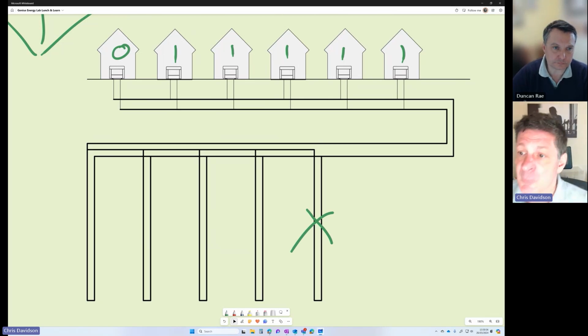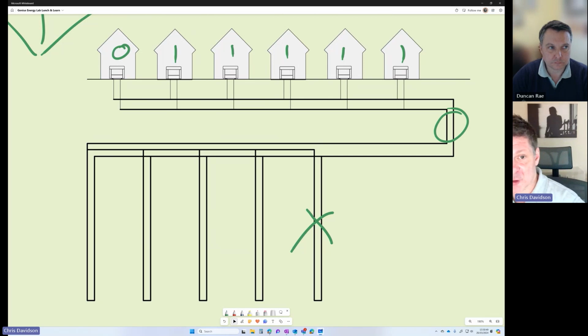On the other hand, the water required for all those heat pumps has to be accommodated in the header pipes that transport water from the buildings to the ground and back, and therefore these pipes get bigger. So there's a penalty to pay in terms of pipe sizing and installation cost.